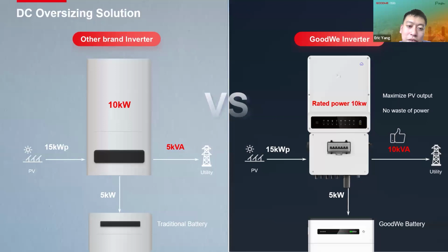And if we look at some other brand inverters, they also write the PV capacity, and it can connect 15 kilowatts of PV panels, but if they have a 5 kilowatt AC output, it can only charge the battery at 5 kilowatts because this is a 10 kilowatt hybrid inverter. If the AC output of this solution is 10 kilowatts, it cannot charge the battery at the same time.